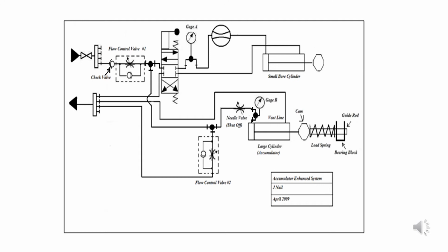In the lower part of the circuit, flow control valve number 2 is simply a safety measure. In the event that oil should be trapped in that line for any particular reason, it can be safely bled down back to the return manifold.